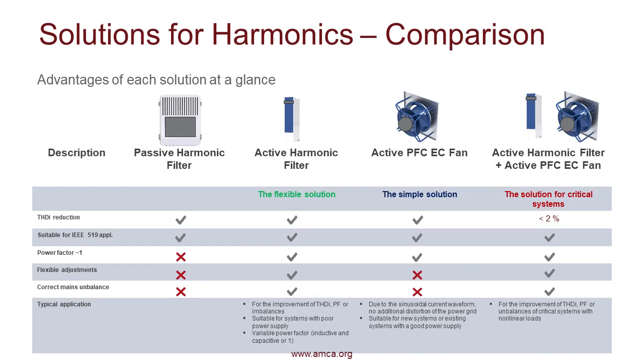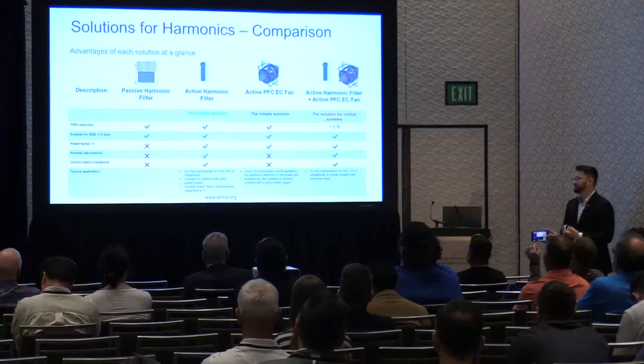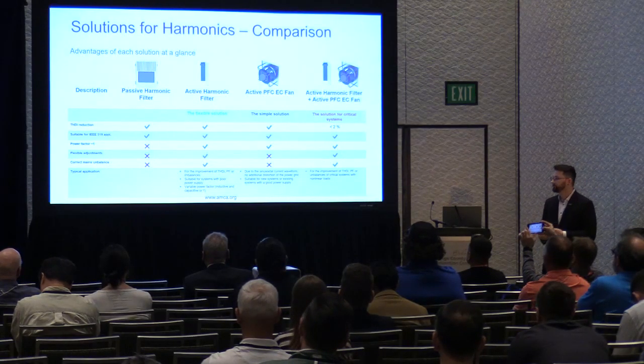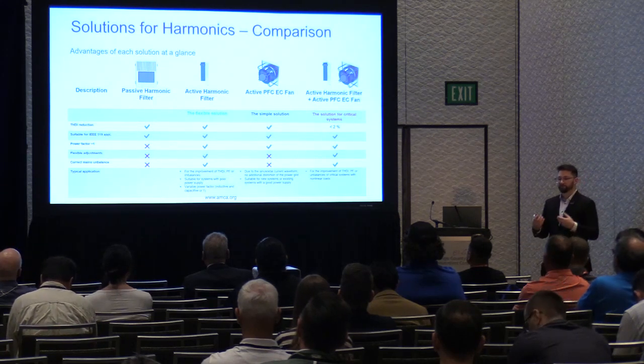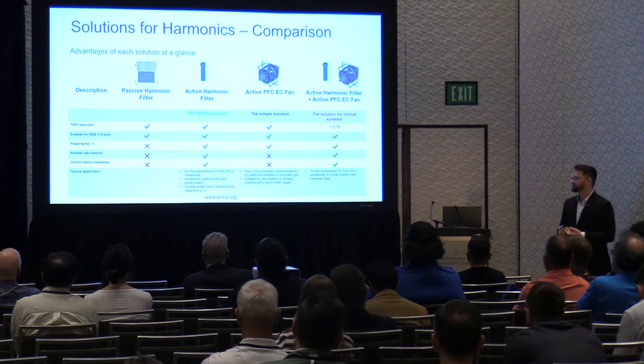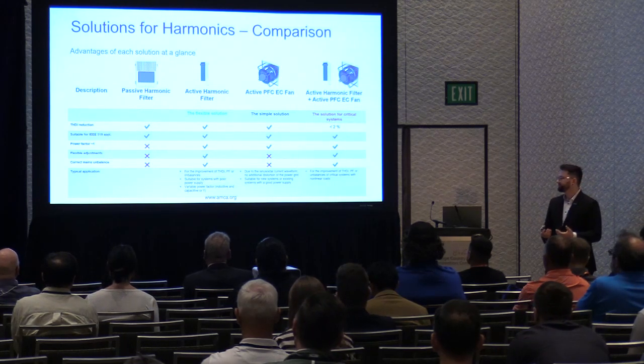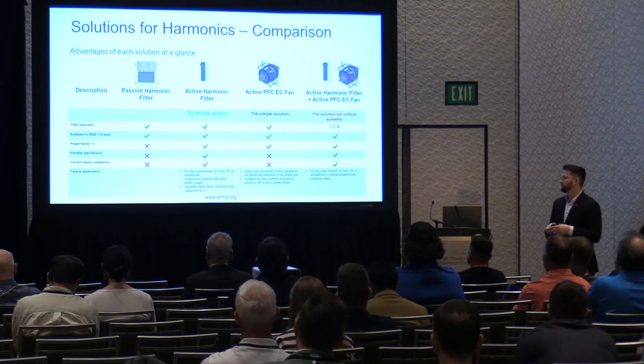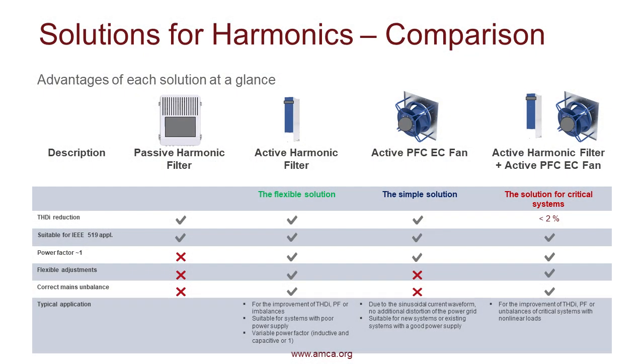So now we can look at a comparison. So we have passive harmonic filters, which reduce your total harmonic distortion current. They're suitable for IEEE 519. They're not increasing your power factor, and they're not necessarily flexible as your site and your grid is changing, the equipment's changing, harmonic loads are changing, and they're not really correcting your mains unbalance, but they're a suitable solution in certain situations. And then we have our active harmonic filter solution, which is maybe your most flexible solution because it can be calibrated for different sites, different systems, different things that are happening, changes over years. It's suitable for IEEE 519.